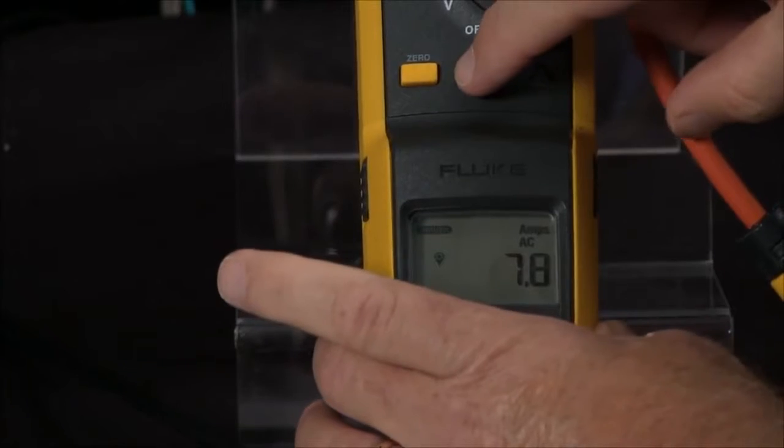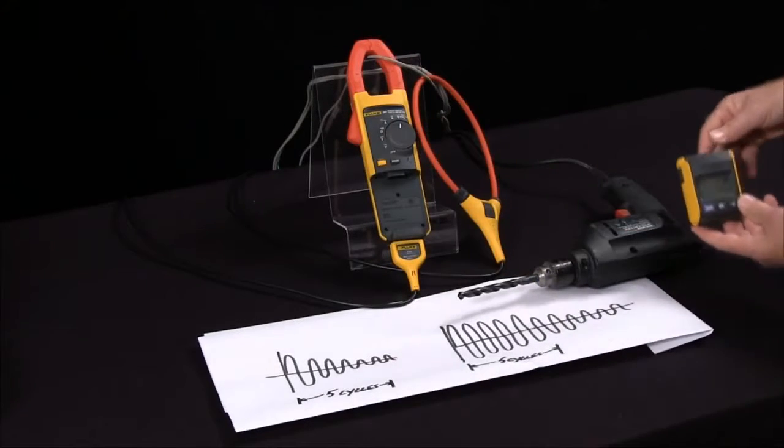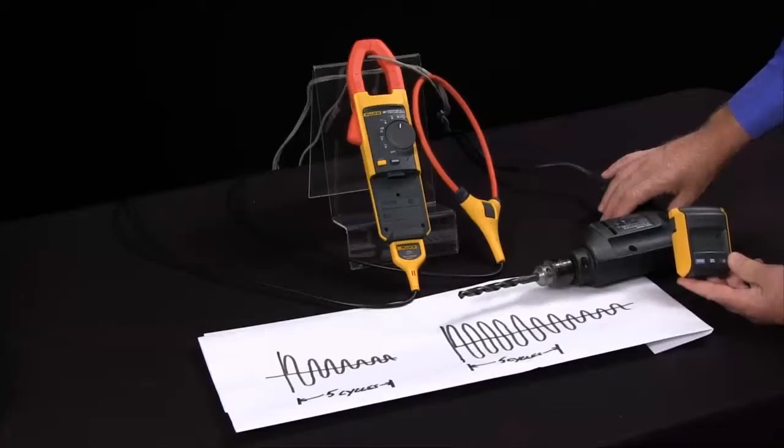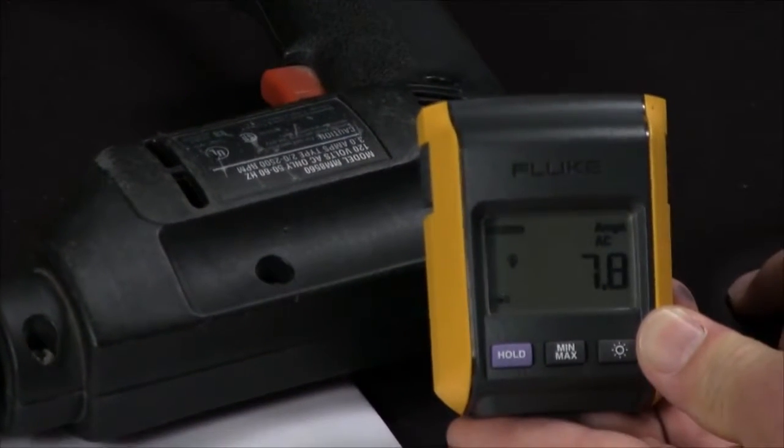Another great feature of the Fluke 381 is you can set the meter to inrush, pull the display over to where the motor start cabinet is, start the motor, and get the inrush current remotely.